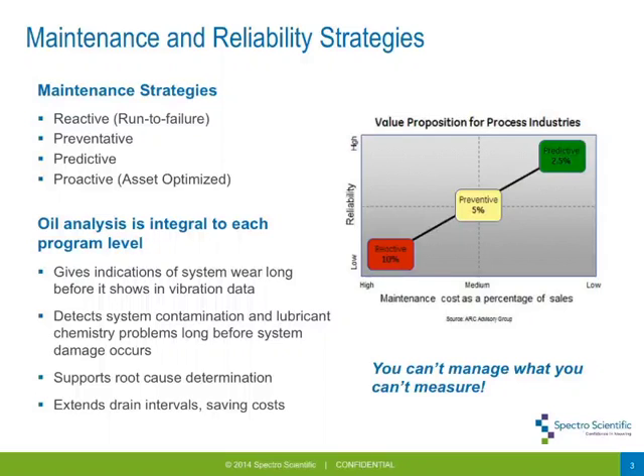Where's a great place to start if you're a fleet maintainer or in industry? We suggest oil analysis, because it's integral to every part of a maintenance program, particularly with oil-wetted components. It's very powerful and a fairly easy technology to get involved with. It gives indications of system wear long before vibration starts to kick in. You can catch system contamination and lubricant chemistry problems before damage occurs, and it supports root cause diagnostics when a problem is occurring. You can also extend drain intervals and reduce practical maintenance costs.